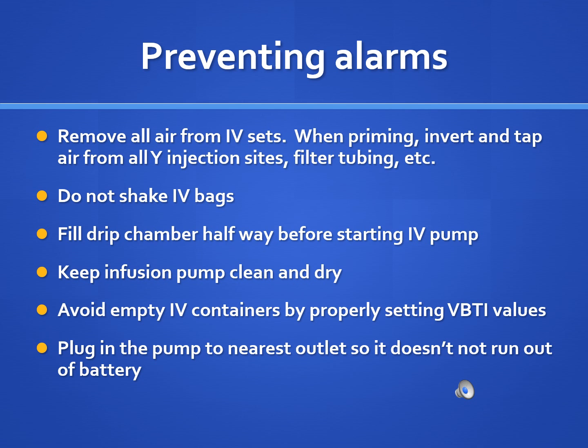Always fill the drip chamber about halfway and no more. You'll always want to make sure the IV pump is clean and dry, especially that tubing channel area. Always avoid empty IV containers by setting the volume to be infused properly. And then always plug your IV pump into an outlet if possible to avoid that low battery alarm.